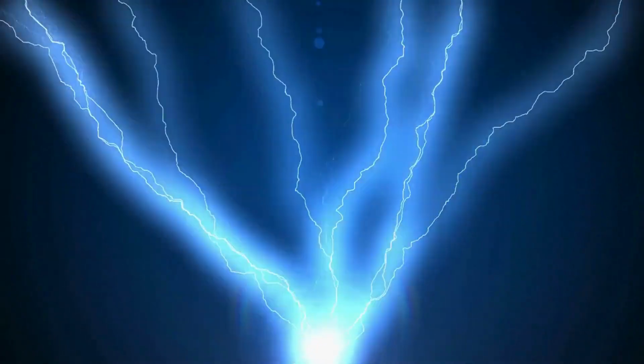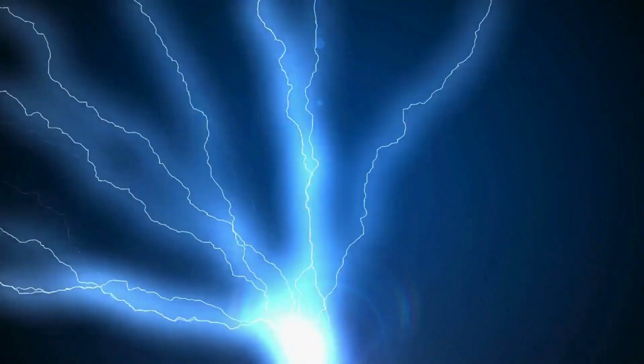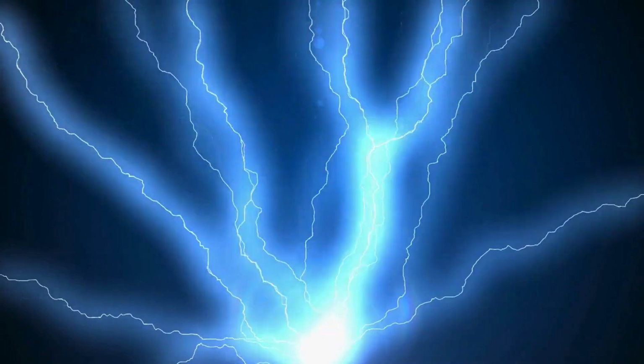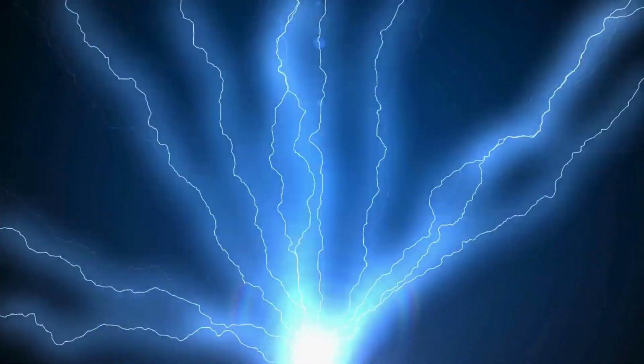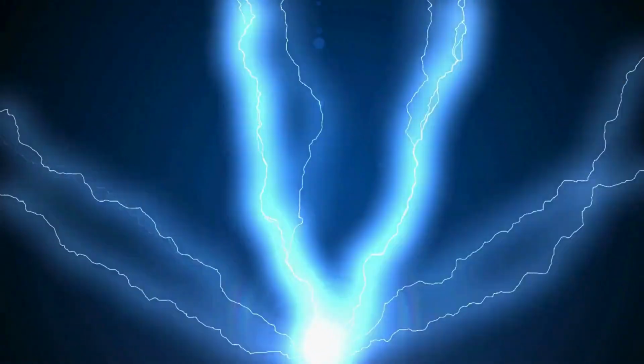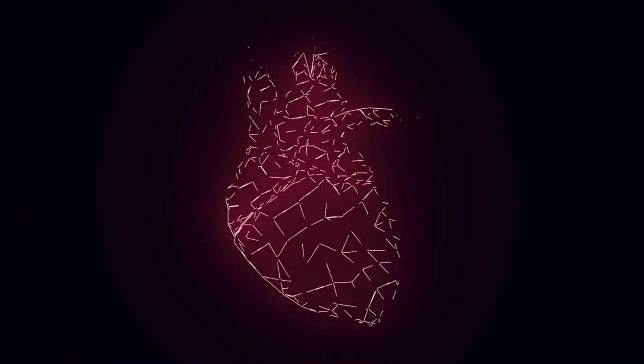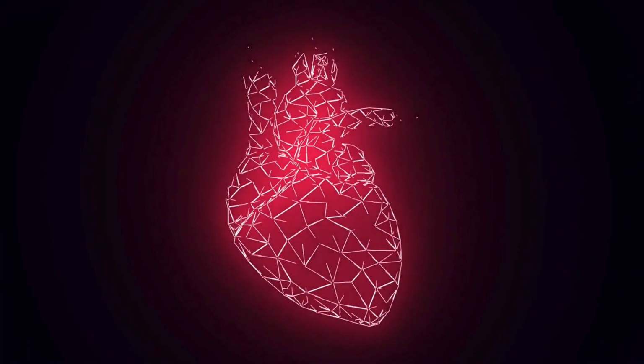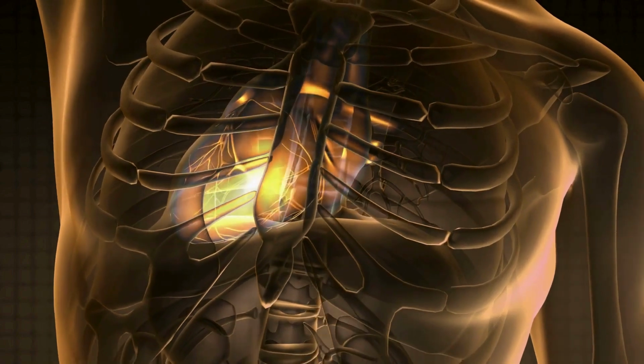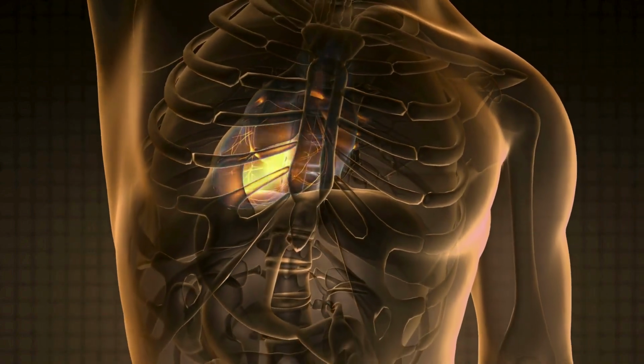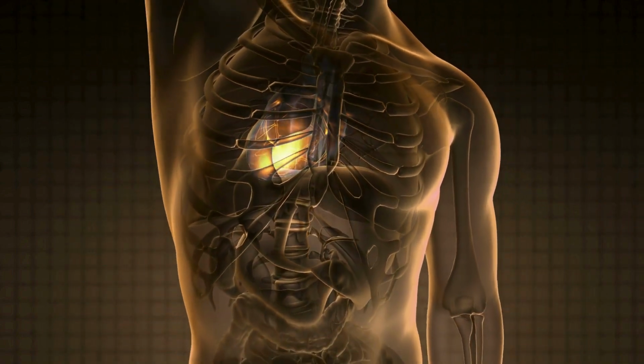The scariest part about capacitor discharge is the speed and intensity. Unlike touching an energized circuit where you might have a split second to pull away, capacitor discharge happens instantaneously. All that stored energy dumps in microseconds. Your muscles don't have time to react. Your heart doesn't have time to adjust. If that discharge path goes across your chest, you're looking at potential cardiac arrest from what you thought was a dead circuit.